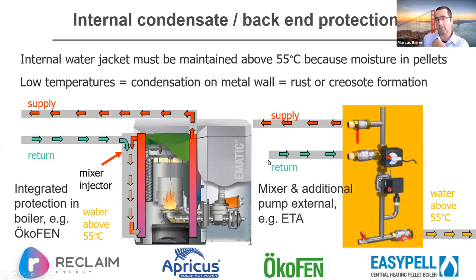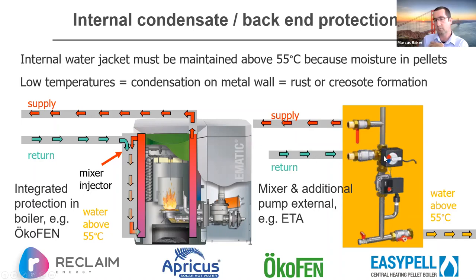Other systems — this is an ETA example — have a mixer and an additional pump. To start with, a lot of the supply hot water from the boiler is mixed back in, essentially closing the loop so the boiler heats its own water until it reaches a good temperature, then slowly reintroduces returning water. There's also pump control — the circulating pump doesn't release before 60 degrees.